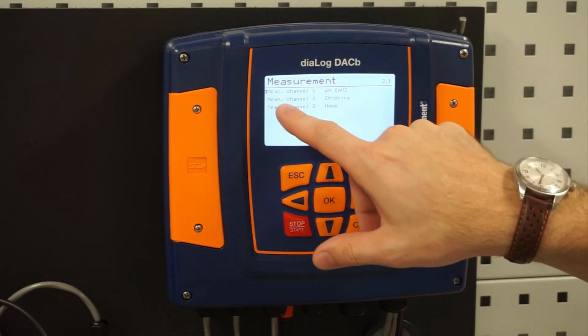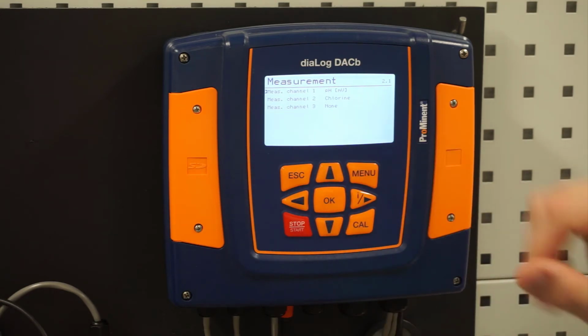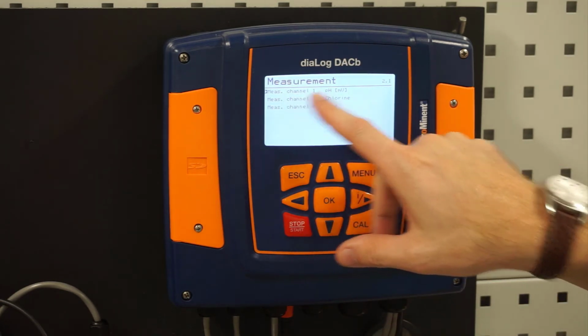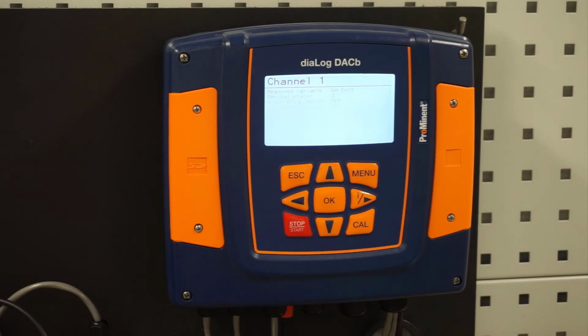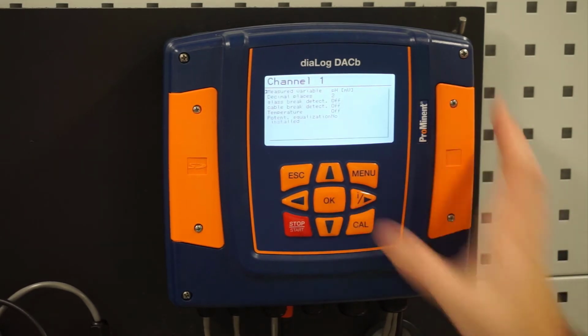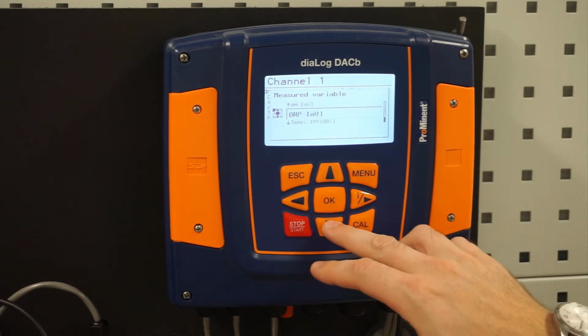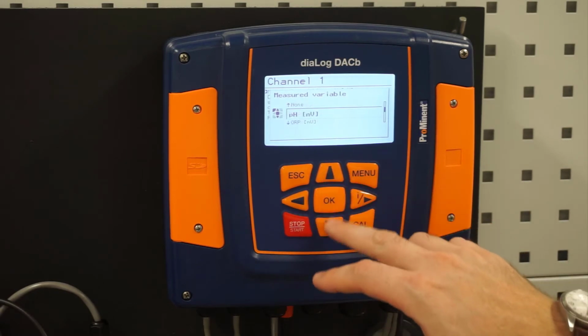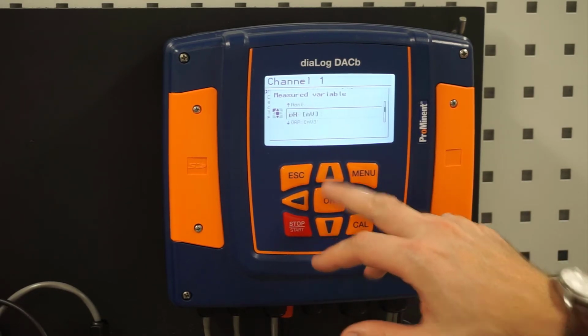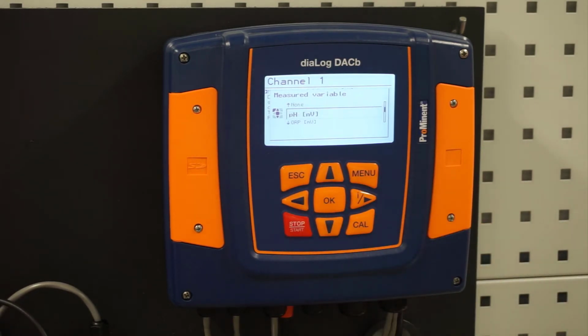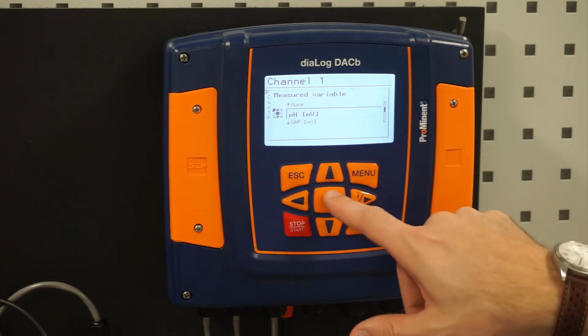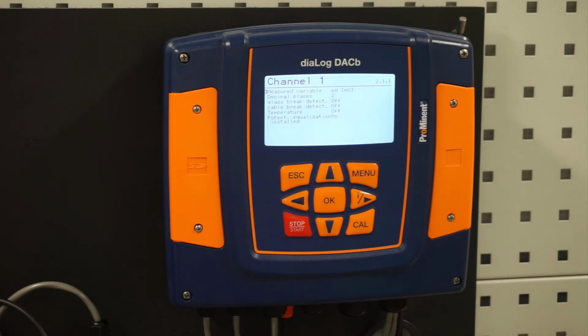But it's good to go in there and make sure it is set up correctly. So on channel 1 we have pH, so if we go in there, we can go into measured variable and we could change that from pH or ORP or temperature. Those are the only options you have available on that millivolt channel. We want to leave it set up as pH.